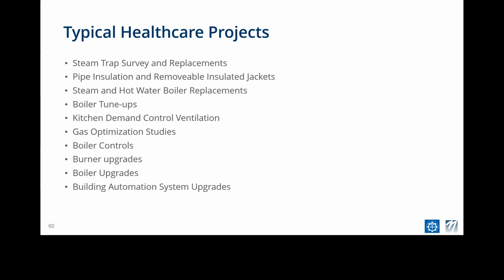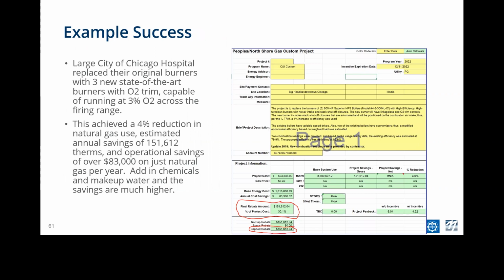Let's see what's next. Just an example — I can't name the hospital, but here's why you'd want to work with us. A hospital in the city has 5 boilers: one for redundancy, one for expansion, so we couldn't touch those two, but the other three were running the building. We upgraded 3 of the burners from the original basic burners to state-of-the-art burners able to run at 3% O2 with O2 trim built in.